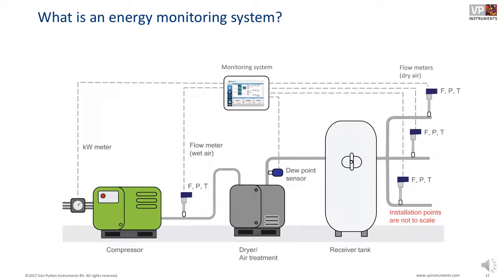And we also have 3 other flow meters. These flow meters can either be our VP Flowscope thermal probe or our new VP Flowscope M. If we talk about the thermal probes, we use the Modbus RTU connection and connect them through a daisy chain to our monitoring system. With the VP Flowscope M, we can choose to make use of Modbus TCP. Then we do not directly connect the meters to the monitoring system, but we connect it into the company network. So we need an Ethernet plug nearby, and we just run a cable from the meter into the company network. Remember, if you do use the Flowscope M, it needs an IP address. So make sure that you talk to the IT guys before you go implement them. You will need to get IP addresses through those guys.